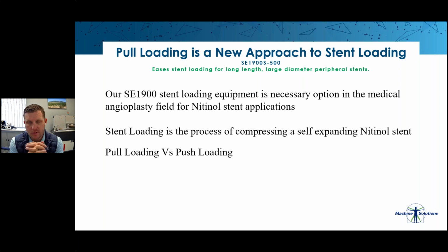One of the benefits of using the pull loading machine is that you can protect the crowns during the loading process, and this becomes very important when the compression forces are high in larger diameter stents. When you start to push load a larger stent above 10 millimeters, there is typically higher compression due to the increased thickness of the strut rows. This can create stiction and the stent can become lodged inside the crimp head. As the quill pushes on the distal edge of the stent, it can damage the stent. Crimp pulse does help reduce radial forces applied to the stent, but there are times where crimp pulse is not enough and the pull loading option becomes the best option.